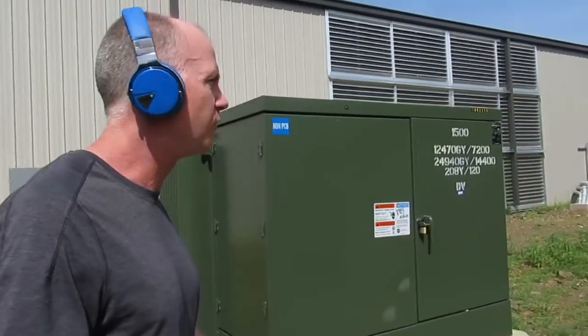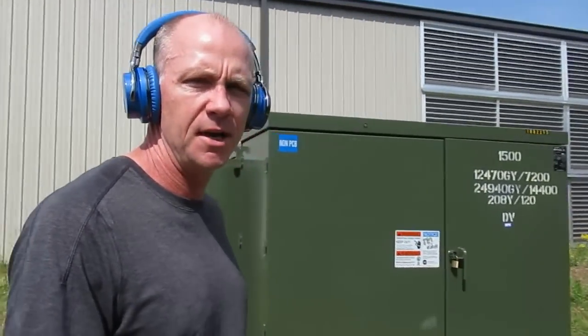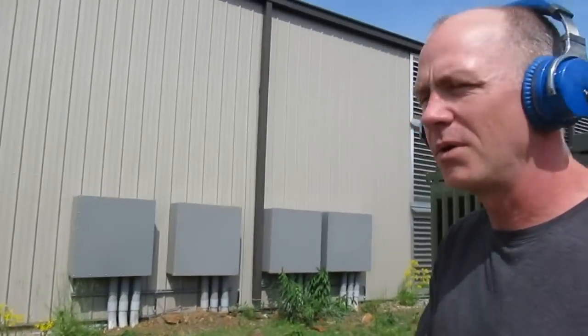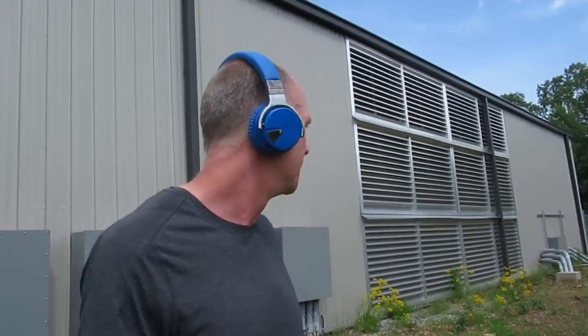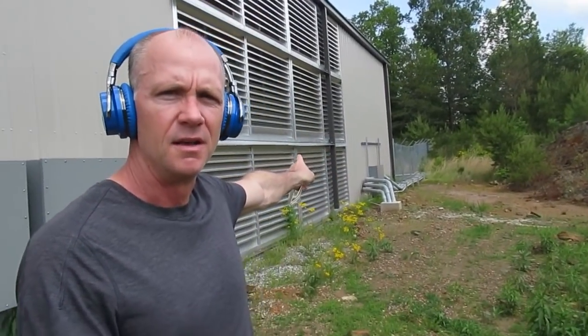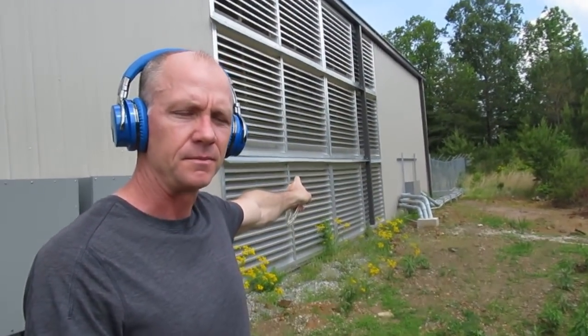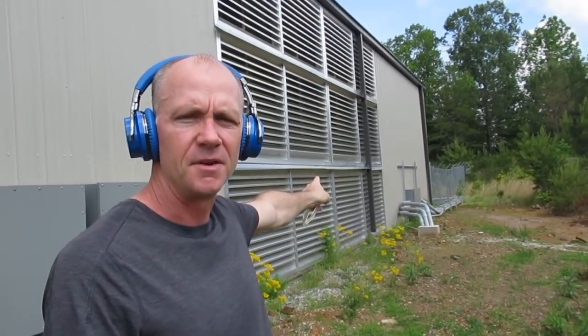Here we've got a transformer that's 1500 kVA at 208 volts, three-phase. Probably next time we do this, we would do a 2000 kVA transformer. It's going to 4 1200 amp panels, and you'll see those inside. The service disconnect is here on the outside. You'll see we cut holes in the wall, and we have vent and filter combination so that we can bring in 180,000 cubic feet per minute of air, and the vents are there so it doesn't entrain water, and the filters are inside to cut down on the dust.